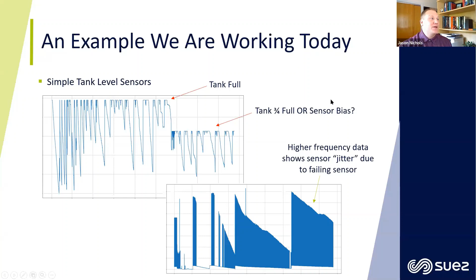Second, when you're looking at smoothing and high frequency data, sometimes sensor failure modes happen at much higher frequency than the frequencies of your twin, so you have to look for those as well. Model those sensor faults and include them in the state definitions for the twin. Use all of the digital data that comes off transmitters for sensors, and where possible, have a physical model predicting what the sensor outputs should be in a multivariate way so you can detect sensor faults as well.